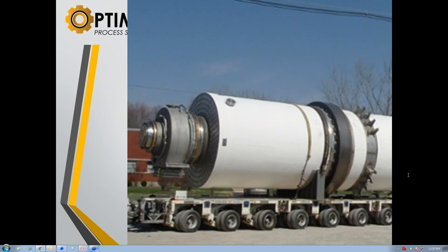You see on the end of that dryer, there's some plates. If there's a steam leak in that dryer, the one that had the bunch of tubes is one that we don't manufacture that often in that configuration. But normally you're going to have a steam manifold, and it's going to have these cover plates on the front of it. These are hand hole covers. This plenum is about a foot thick, and there's a tube sheet in here that the tubes are rolled into. So if you have a tube leak on that dryer, you can pull that hand hole cover off, and you can actually plug that tube, and you can go back and run until you have the time when there's an outage.